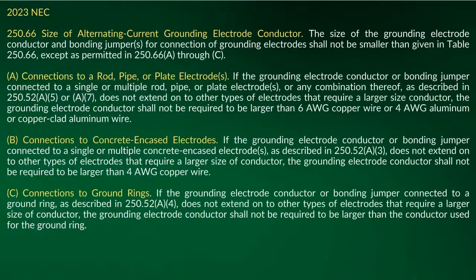And I just wanted to start with the 2023 250.66 because they made some changes. And they tell you right in the heading, it says the size of the grounding electrode conductor and bonding jumpers for connection to grounding electrodes shall not be smaller than given in the table. Then it says, except as permitted in 250.66(A) through (C). What they're telling you here is they don't want the table being used, period.